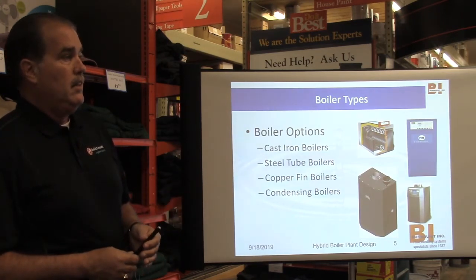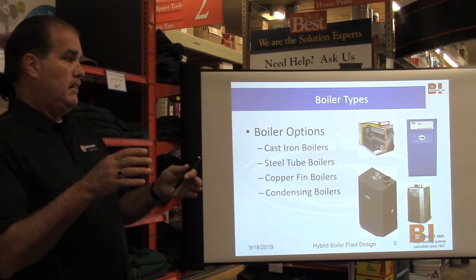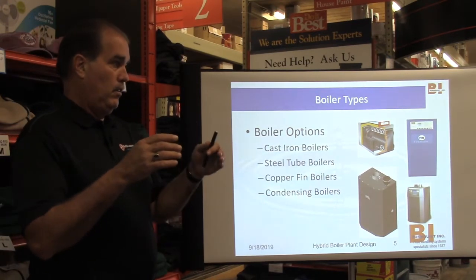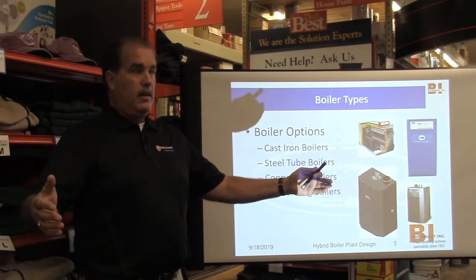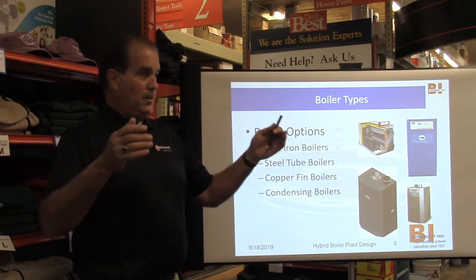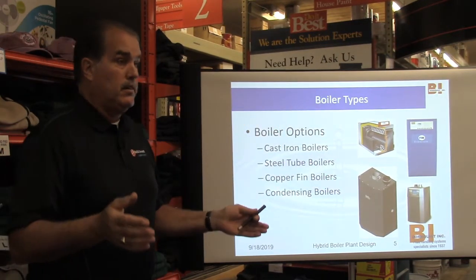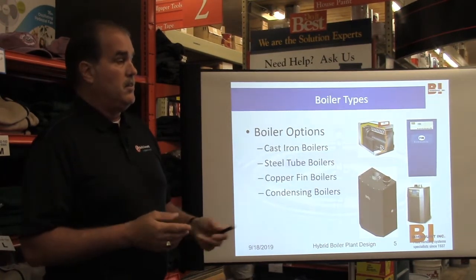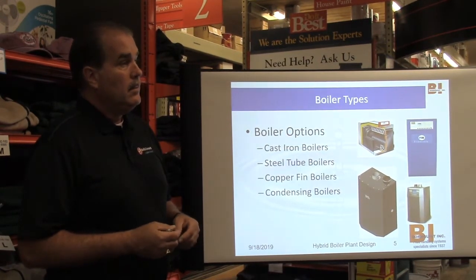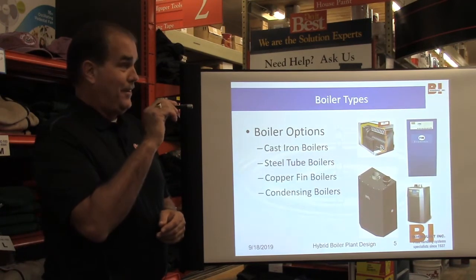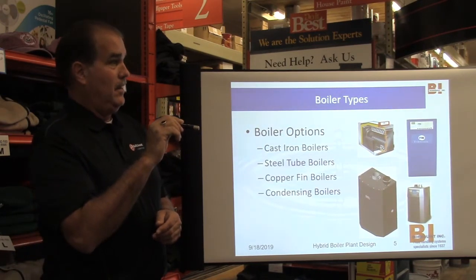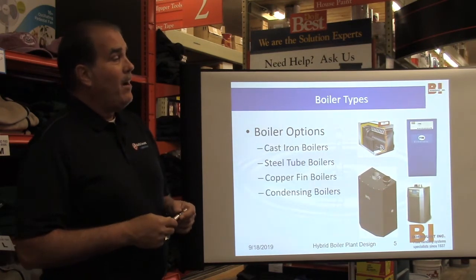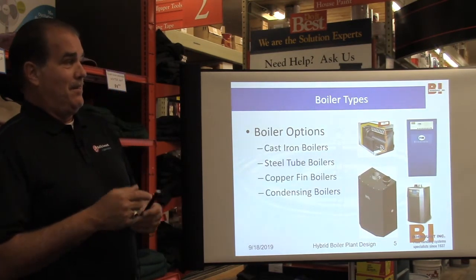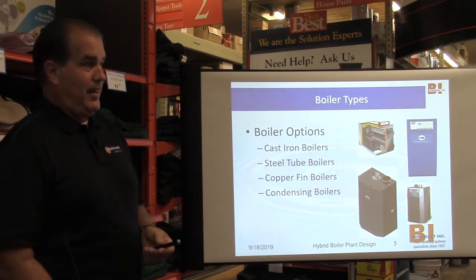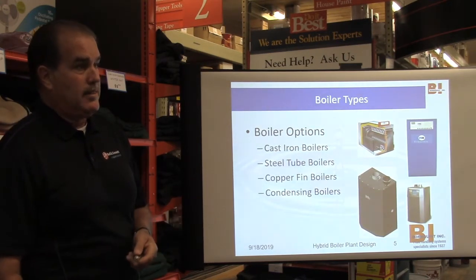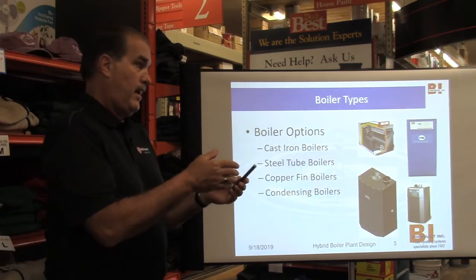Don't be concerned, because they're designed for a certain BTU rating. So the boiler that was there before that was big could have been 100,000 BTUs. The boiler that they're putting in now is going to be smaller, but still 100,000 BTUs. So it's going to do the job heating your building. If they know how to calculate it, yes. Typically what happens with the replacement boiler is a guy's going to walk in, look at the nameplate of the boiler that's there and say, okay, I'm going to get you one that size. Or if they don't have one that fits that size, maybe a little bigger.